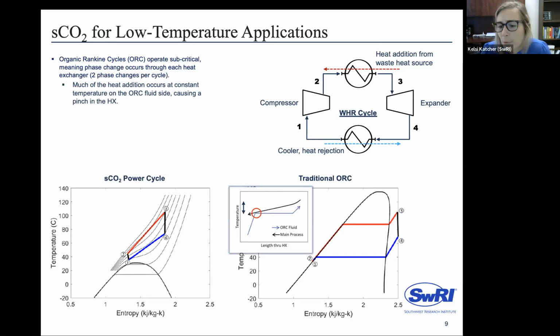The main problem with this is that if you follow that temperature profile, you're increasing in temperature, then adding heat, continuing to add heat, but not adding any temperature—you get that knee in your temperature profile, which causes a pinch inside your heat exchanger. If your ORC fluid follows the blue curve on the thumbnail plot, and your main process flow—heat rejection from your waste heat fluid, or brine coming up from your geothermal well—as you're heating your ORC fluid, you're pinching against that knee. So you're not able to get as much temperature change in your process fluid, and you're not able to get as much heat into your ORC fluid. That really limits how much power you can get out of your ORC cycle.